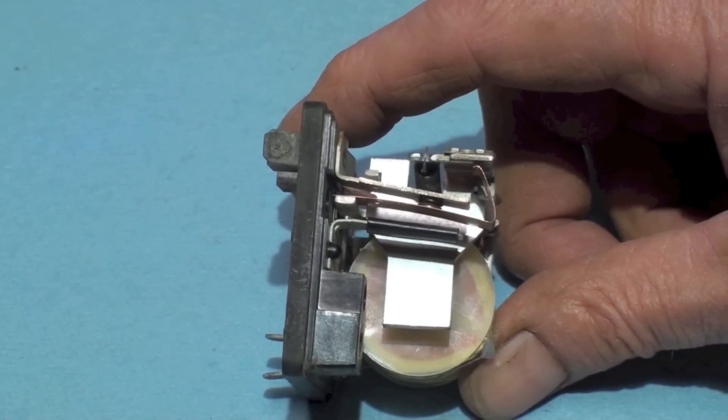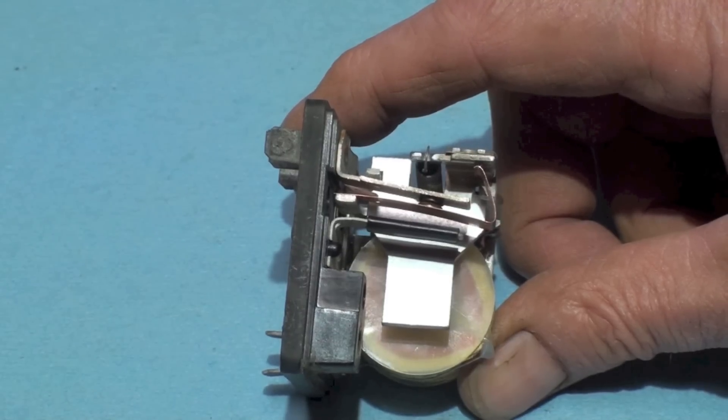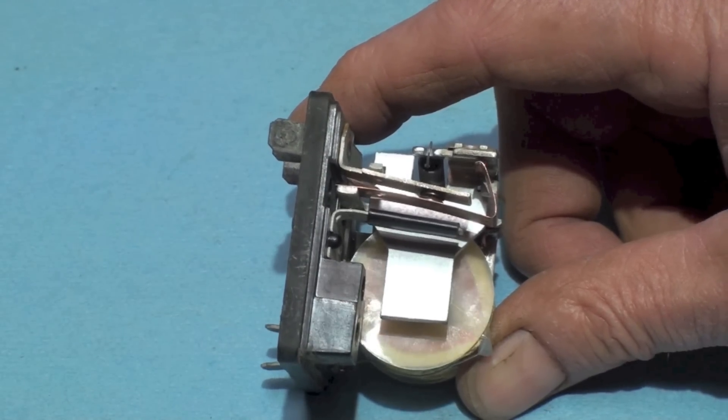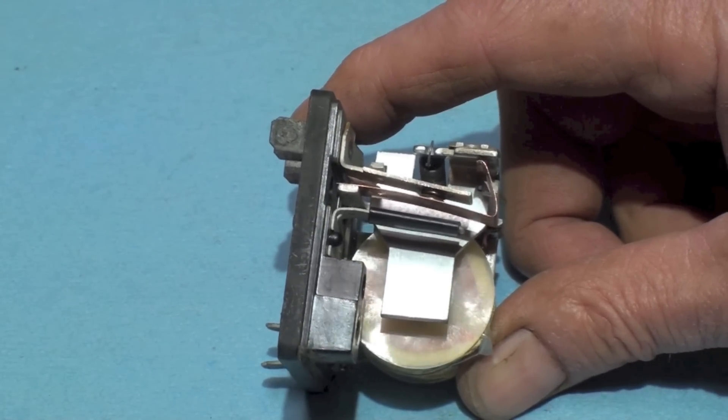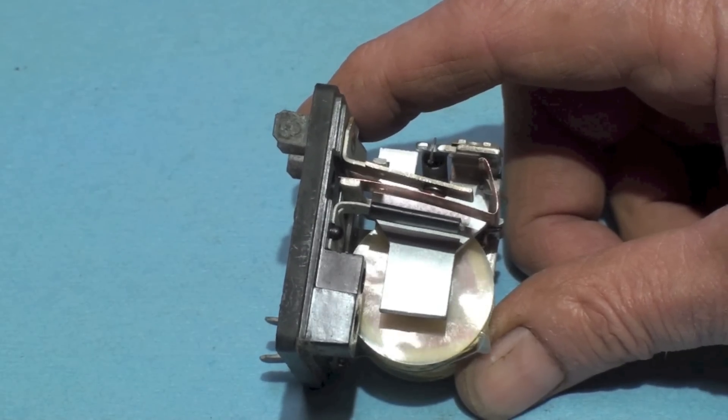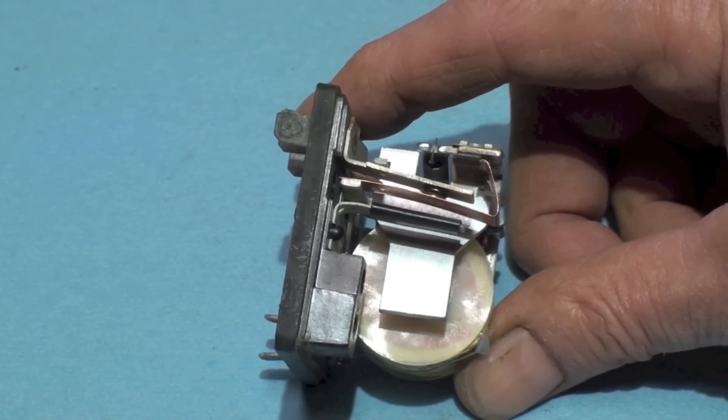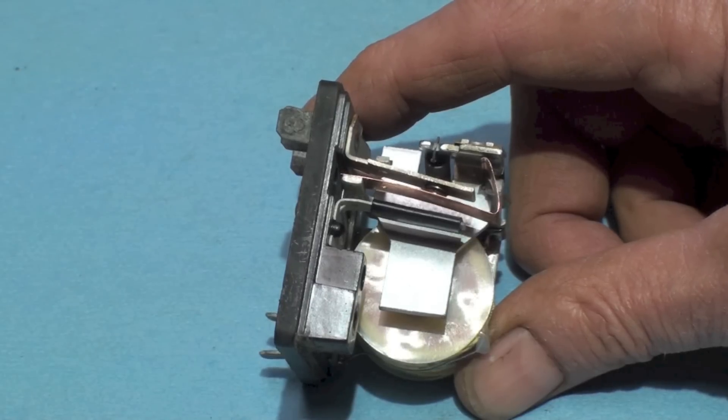Let's say I have a 240 volt circuit. The back EMF stacks on top of the voltage supplied to the unit, so this thing will be somewhere between 350 and 400 volts before this closes down.